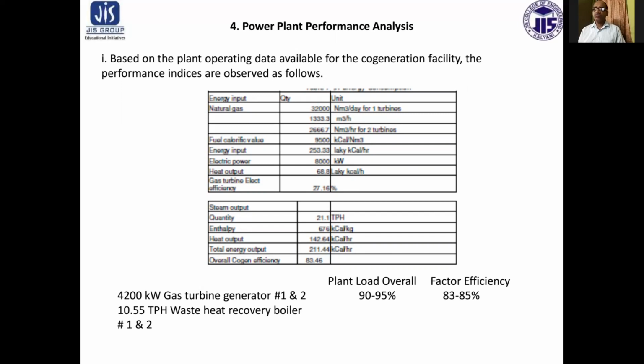Electric power 8000 kilowatt. Heat output 68.8 lakhs kilocalorie per hour. Gas turbine efficiency is 27.16%. The steam output quantity 21.1 TPH, enthalpy 676 kilocalorie per kg, heat output 142.64 kilocalorie per hour, total energy output 211.44 kilocalorie per hour. Overall cogeneration efficiency is 83.46%.